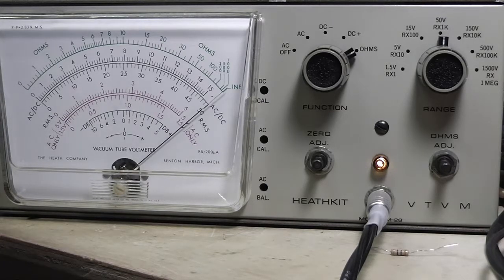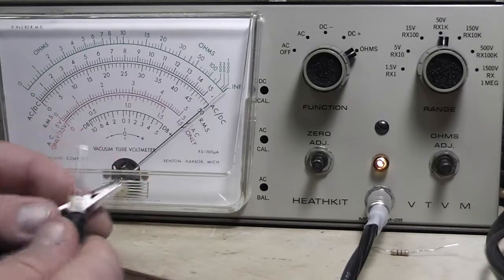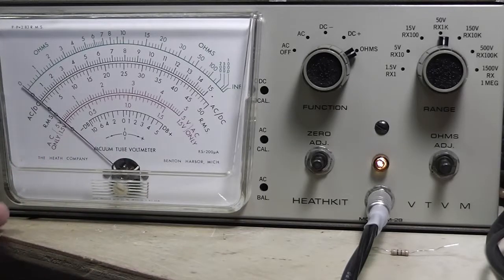So it says set the probe switch to AC ohms and touch the probe to the common test clip. The meter pointer should drop to 0 at the left end of the scale, no resistance. So what they're saying is, if I touch these two together here, it should come back down to 0, and it does. Then you go and it goes back to there. And that's all they go over on that.